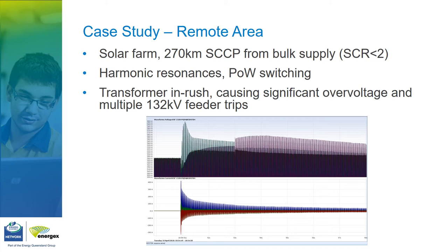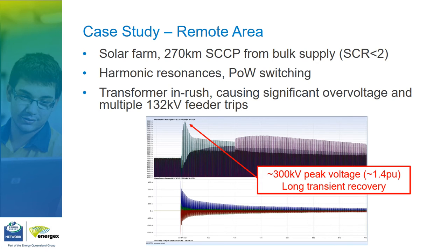So in our case, we required point-of-wave switching due to transformer energization risks. And luckily we did, because attempting to energize a transformer without point of wave led to 1.4 per unit overvoltages on the 132 kV feeder, which basically caused multiple trips on multiple occasions.